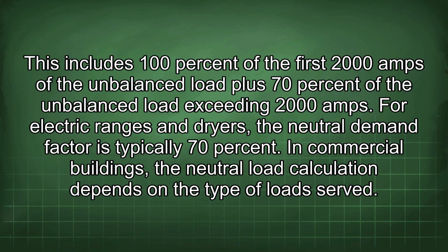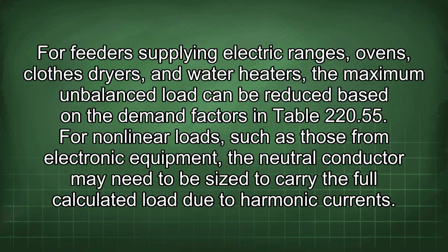This includes 100% of the first 2000 amps of the unbalanced load plus 70% of the unbalanced load exceeding 2000 amps. For electric ranges and dryers, the neutral demand factor is typically 70%. In commercial buildings, the neutral load calculation depends on the type of loads served. For feeders supplying electric ranges, ovens, clothes dryers, and water heaters, the maximum unbalanced load can be reduced based on the demand factors in Table 220.55.